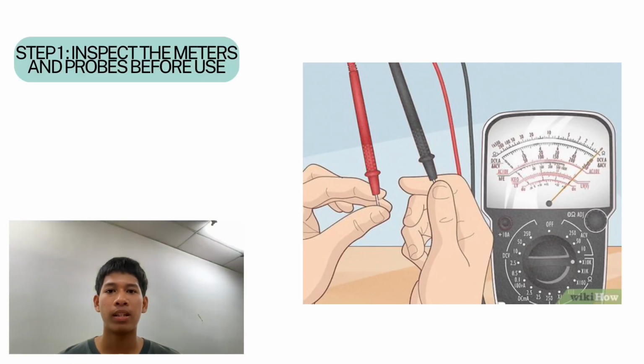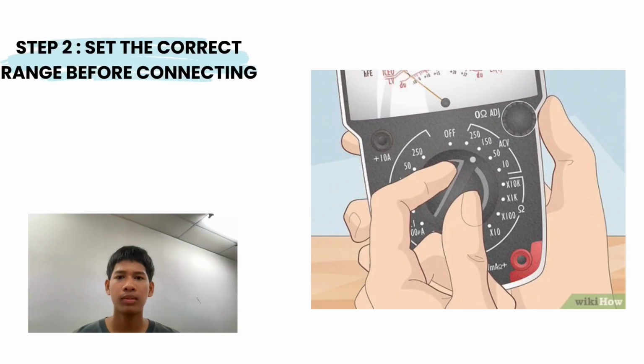Step 1. Inspect the meter and probes before use. The first step is always to inspect the condition of the meter and the test probes. Check the meter body. Make sure there is no crack on the casing or loose selector switch. Look at the wires and probes. Ensure the insulation is not broken and the metal tips are not bent. If there is any damage, do not use the multimeter until it's repaired, because a damaged probe can cause electric shock or wrong result.